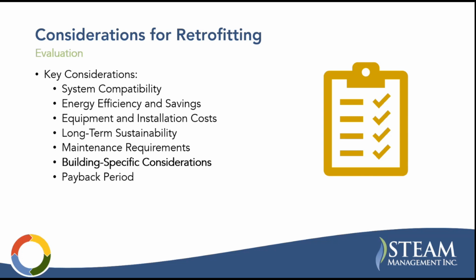Building specific considerations. One of the main things here is a lot of these boiler rooms are designed for old cast iron sectional boilers, which can basically be brought in by hand and assembled in the boiler room. There's been several opportunities where somebody's interested in a condensing boiler, and we go in and there's really no access to the room without doing significant structural or architectural modifications to get the boiler into the room. These are fully assembled boilers. They're not field assembled, and you have to have some way to get in the room.